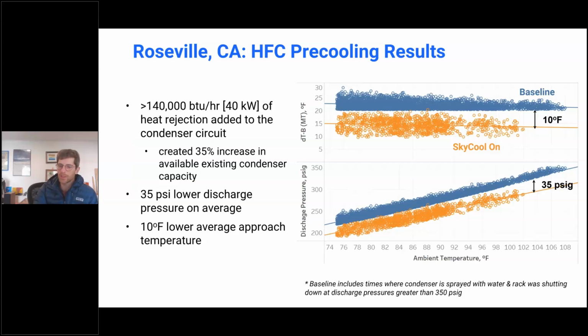So much in the same way as if you were going from an air-cooled condenser to an evaporative condenser, we're essentially doing that, but without using water. And this is still above the dry bulb temperature. We're not approaching the wet bulb, but there's still inherent value in lowering the discharge pressure. So in this case, this was an R404A rack. We lowered the discharge pressure by about 35 psi and lowered the approach by about 10 Fahrenheit.